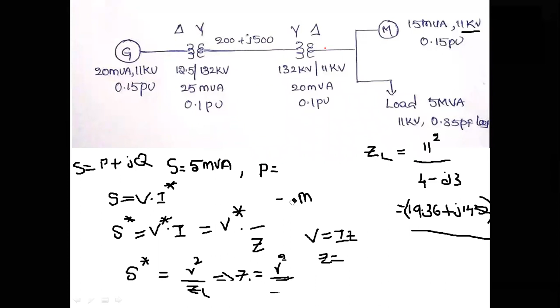So what is the base value? How can we obtain the base value? The base value can be obtained by considering the kV base square divided by MVA base. So Z base is equal to kV base square divided by MVA base. Now what is kV base here? So 11 square divided by 20. Now what is the value you are getting? 6.05.